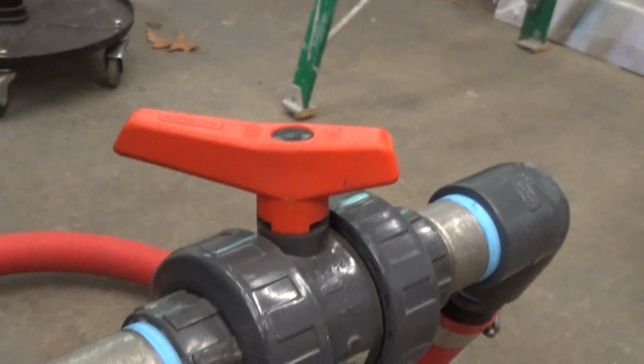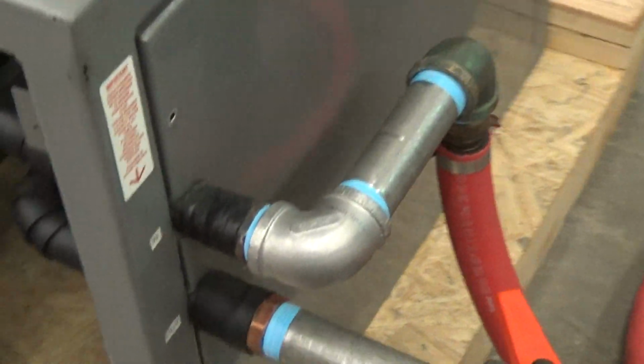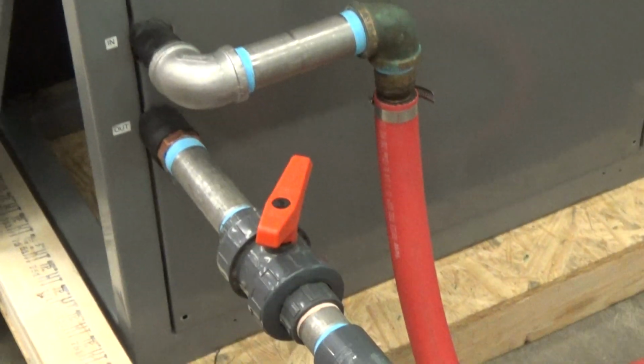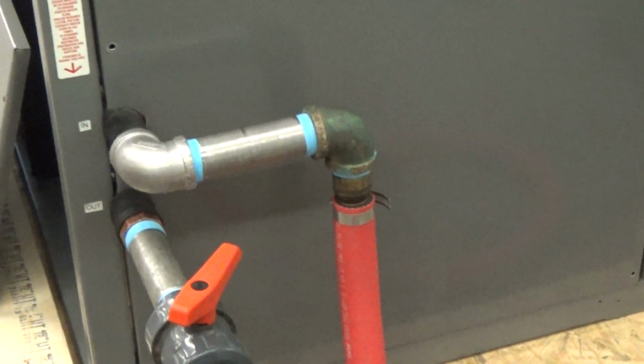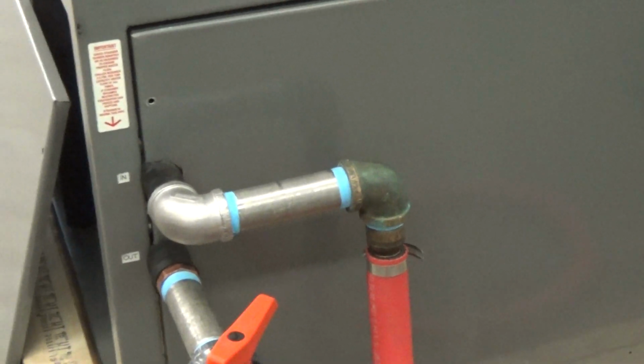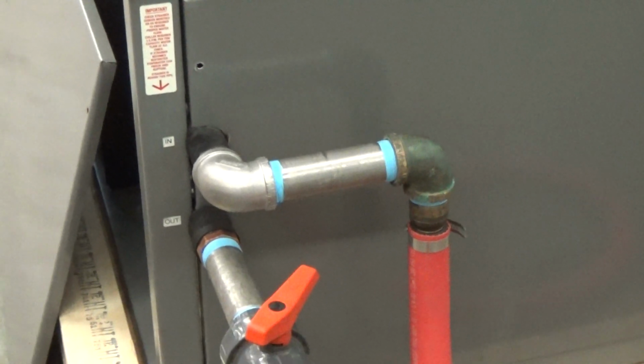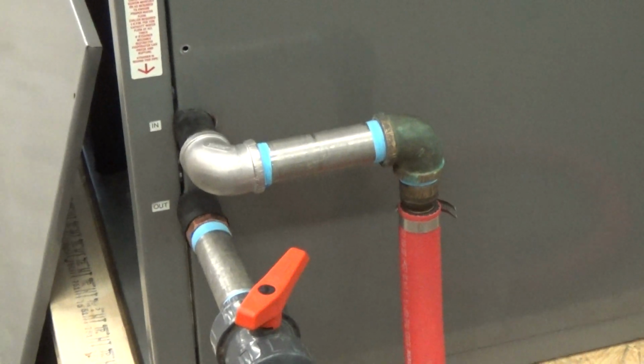The pump draws from the tank and then goes out to the process, and we just have a loop set up here, throttling it back a little bit. On the return, there's a bypass valve here, and we ship that open a little bit. Depending what your process is, if you have multiple machines or a machine that has a solenoid valve on it, and that valve closes such that there's no flow going out to the process, that bypass just needs to be opened enough so that there's enough flow going back to the chiller that that flow switch is made.